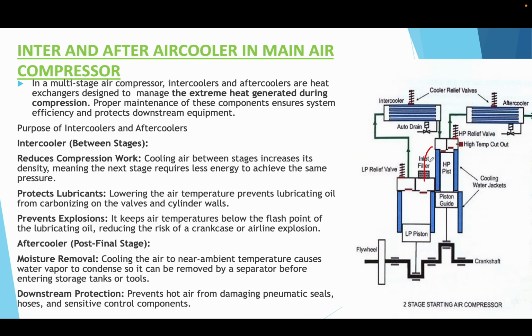So it is flowing like this: suction, discharge, getting cooled, again suction, HP, again discharge, and then after cooling flowing out. So this cooler is called the intercooler because it is in between the LP discharge and HP suction, therefore its name is intercooler. And this is called the aftercooler because it is after the HP discharge and in between the HP discharge and the main air bottle.